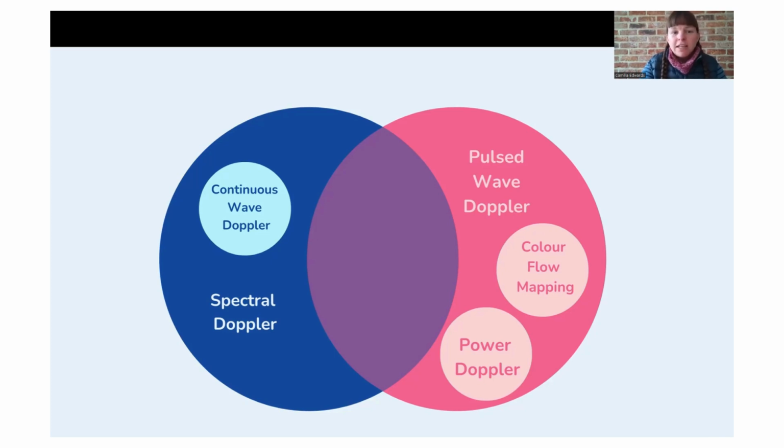And then we have continuous wave Doppler or pulse wave Doppler, which is how these display images are generated. We can either have pulsed wave Doppler, where essentially one piezoelectric crystal in your ultrasound probe emits a sound signal, hits whatever is flowing and comes back to the probe and is sensed by the same crystal. So it knows exactly how far away it hit that and came back to the probe. Therefore it can put the color on the screen exactly where that happened.